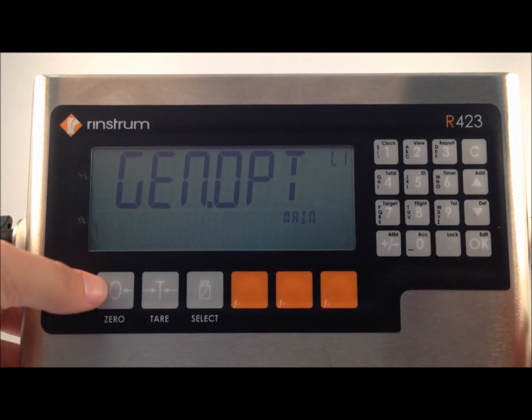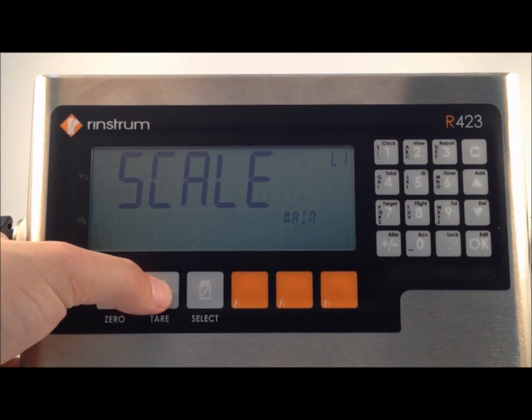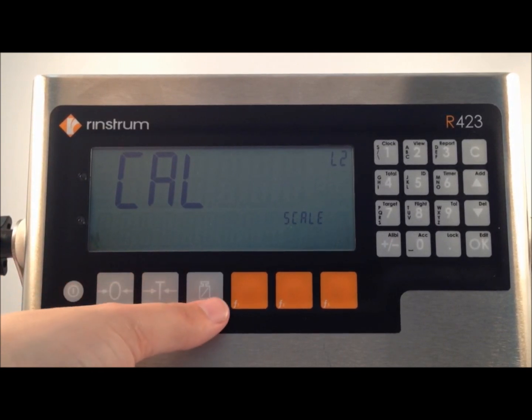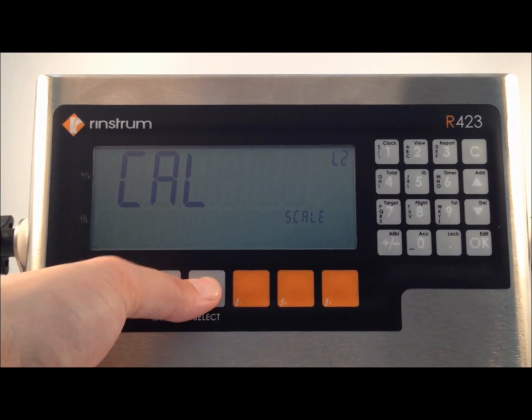We then press the zero key two times to get across to scale. We enter into the scale menu with the tare key, and we press it a further two times to get to cal. We enter into the cal menu with the select key. This can also be the gross net and recipe key in older models.